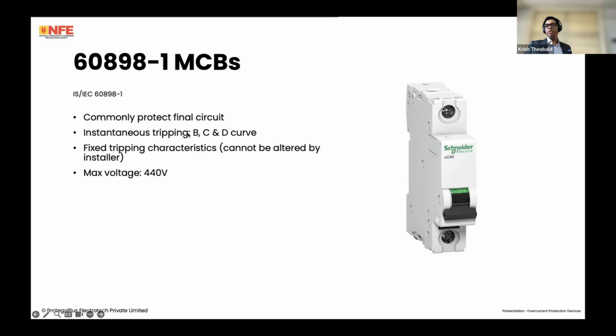As we know, B curve MCBs trip between 3 to 5 times the rated current. C curve MCBs trip between 5 to 10 times the rated current, and D curve MCBs trip between 10 to 20 times the rated current. Sorry, yeah, that's right, 10 to 20 times the rated current. Fixed tripping characteristics, like I said, you only get B, C, and D options with the 60898. You can't suddenly say that you want the breaker to trip at times 8. So if you have a 10 amp C curve breaker, the minimum fault current required to trip would be 10 times 10, which is 100 amps, but you can't suddenly say you want it to trip at times 8, 80 amps.